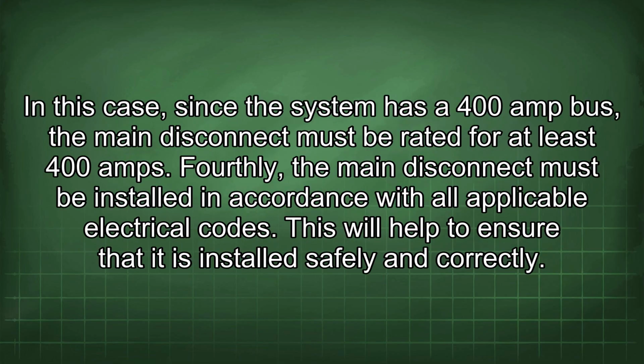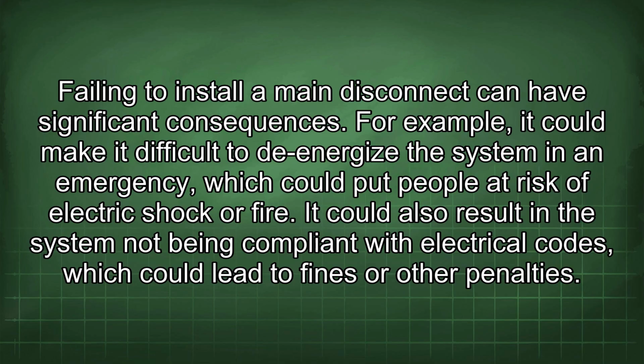In this case, since the system has a 400 amp bus, the main disconnect must be rated for at least 400 amps. Fourthly, the main disconnect must be installed in accordance with all applicable electrical codes. This will help to ensure that it is installed safely and correctly. Failing to install a main disconnect can have significant consequences. For example, it could make it difficult to de-energize the system in an emergency, which could put people at risk of electric shock or fire.